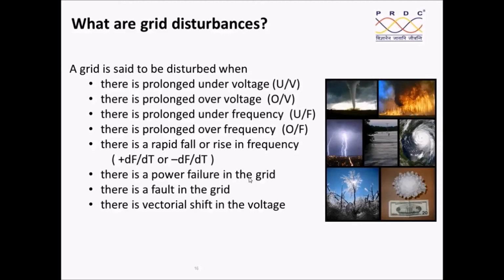I have seen many places where, on a momentary voltage dip, the islanding relay operates. It is wrong. On a momentary frequency dip, the islanding relay operates. It is wrong. Therefore, we have to ensure that for a momentary voltage or frequency dip, that is, a transient voltage or frequency variation, the grid islanding relay should never operate.